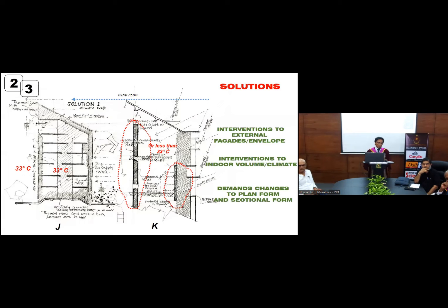Then you can take all hot air to the upper level of the building. The upper level of the building can then be open to the outside, against or with the wind flow, so the wind flow will not disturb this stack flow. Both stack flow and wind flow will work in the same direction.